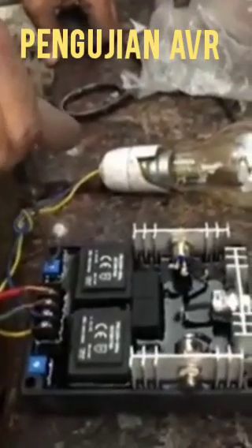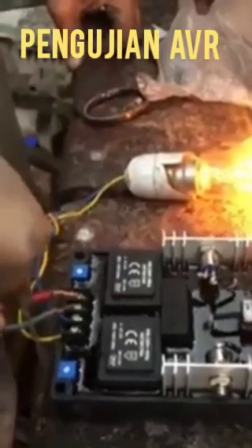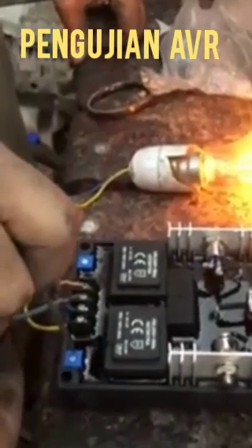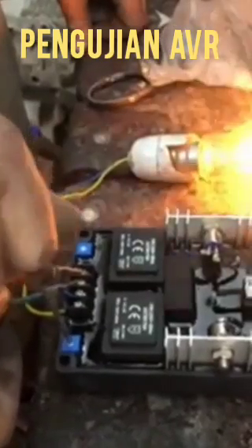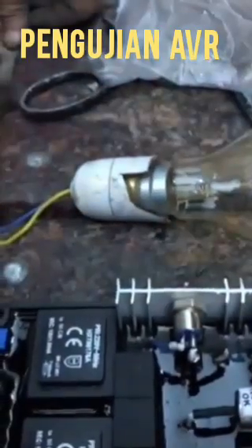We have a connection of the AVR from the alternator F1 and F2, and we connect one bulb from the other two wires. We can adjust the voltage from the voltage pot, and after that we can further adjust it using the variable control, which will increase the voltage.